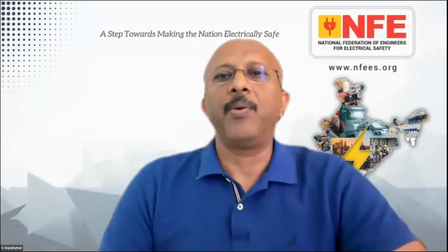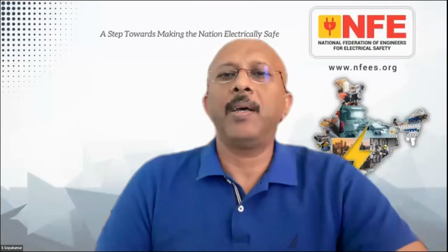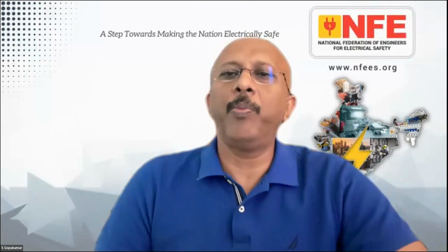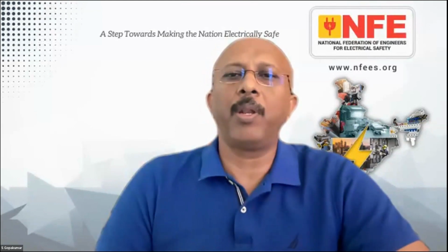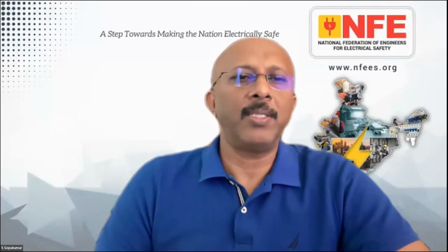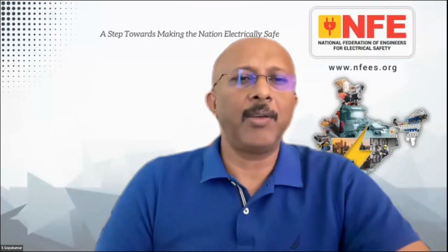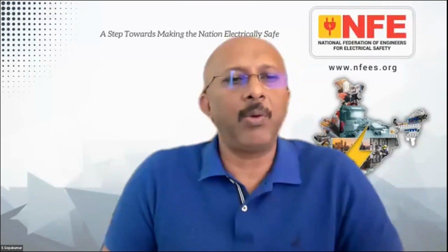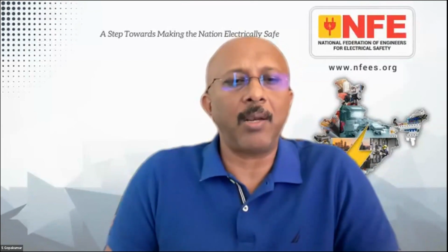Okay, thank you. Now another question. Can we measure the loop impedance of a 3-phase 415-volt induction motor which is in running condition at site? Similarly, can we measure the loop impedance of the transformer LV side when the transformer is in service? So basically the question is, can we do the measurement when these devices are in working condition?